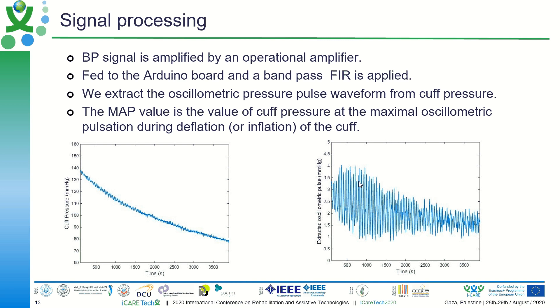From the MAP, we can also extract the systolic and diastolic blood pressure by finding the points at 0.6 and 0.8 of the MAP amplitude value, reflected on the cuff pressure curve. So the MAP at this point is equivalent to some corresponding point on the curve, and the systolic and diastolic are at 0.6 and 0.8 of this value reflected on this curve.